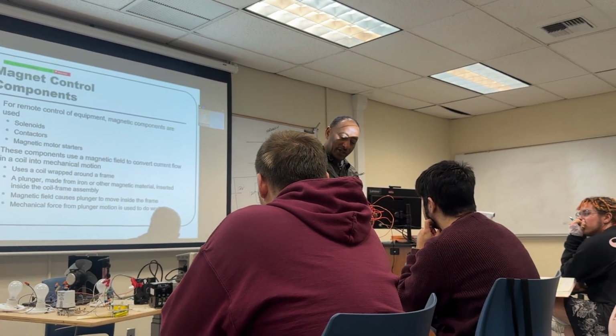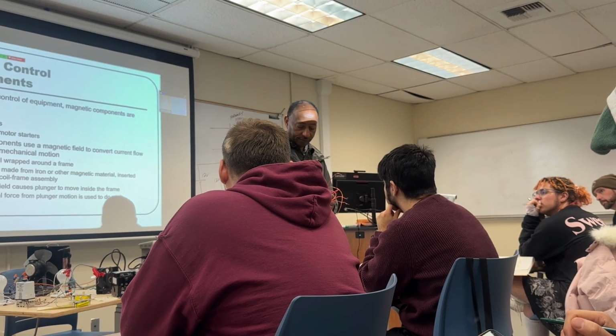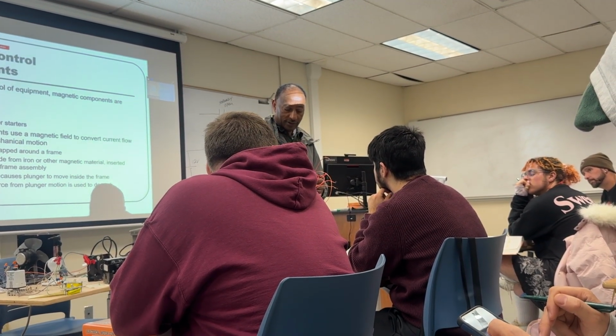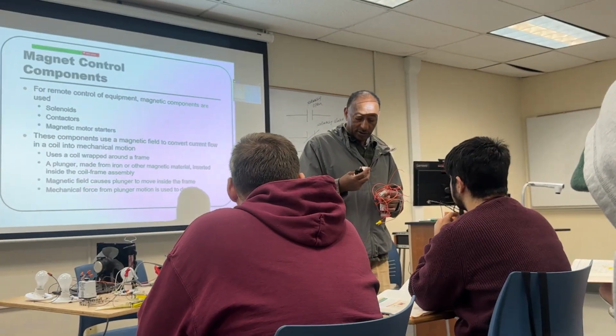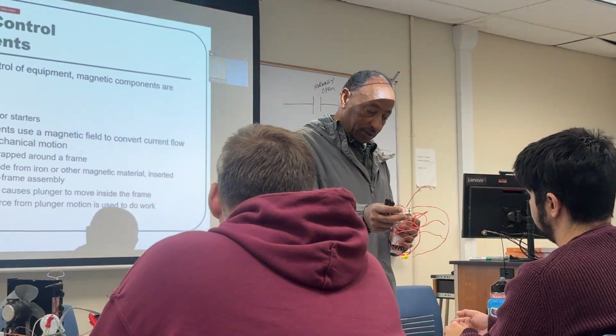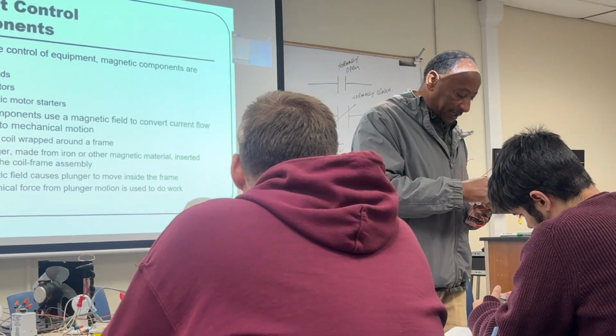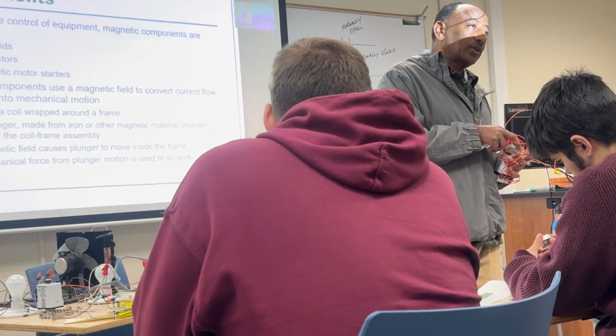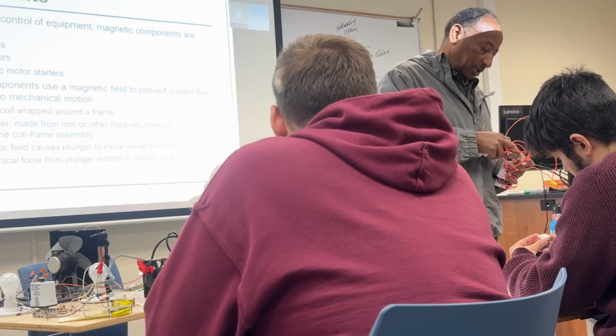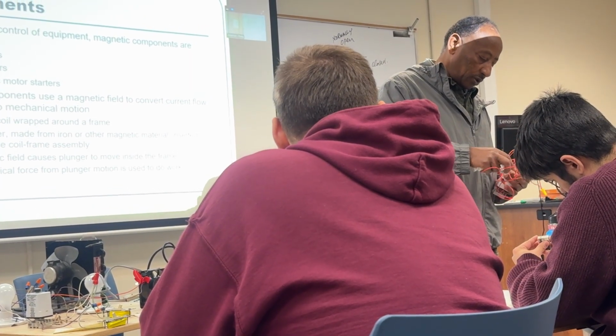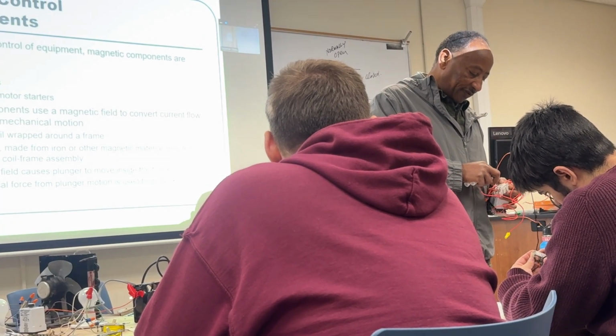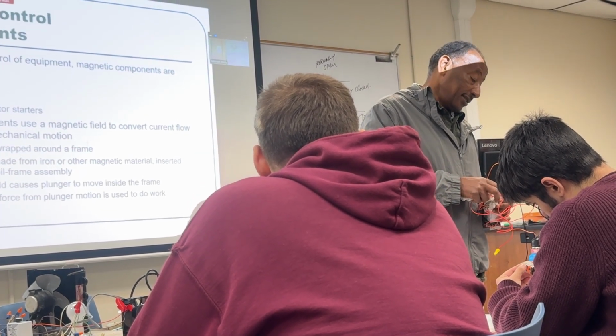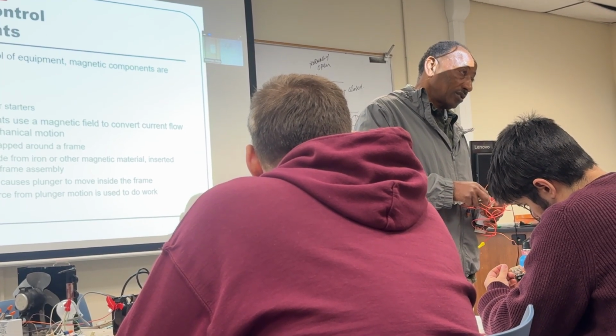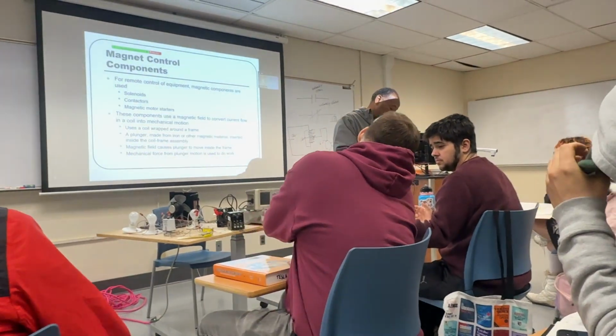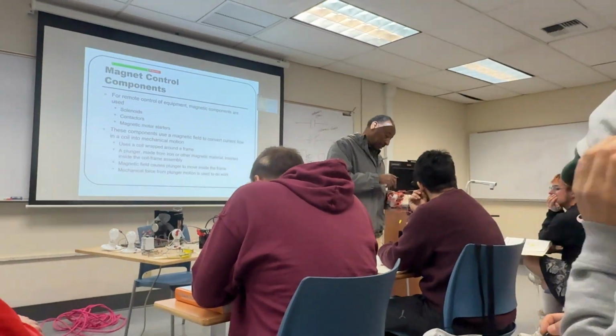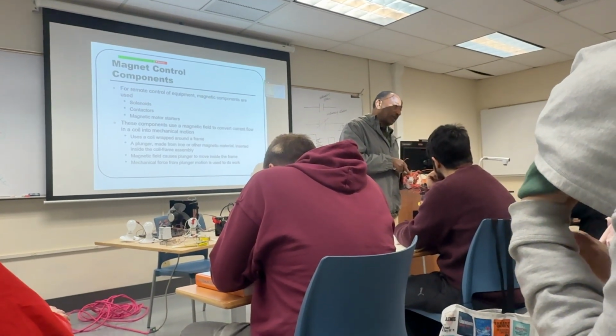This is what's called a solenoid. This takes about 12, 14 volts, DC power. The top part is just to control the solenoid, so you only give it up to 14 volts, and then it can connect 120 volts. The top two are normally closed switches. The bottom two are normally open switches. So I can activate this without activating the solenoid, it's already connected. Then if I activate the solenoid, the bottom one will be connected.